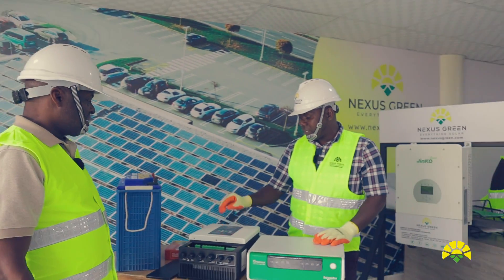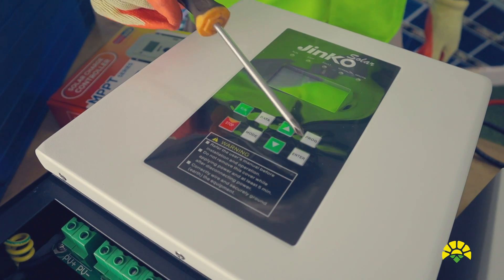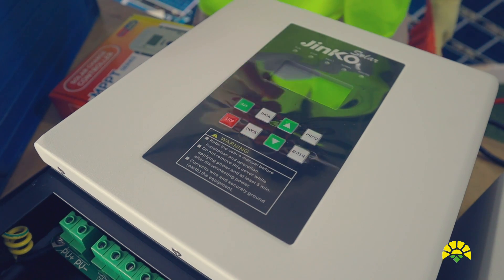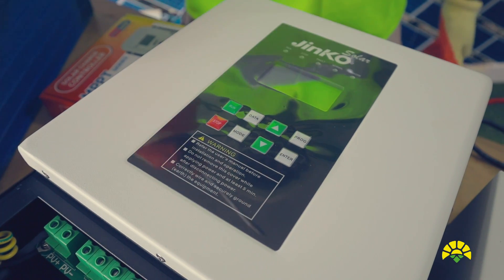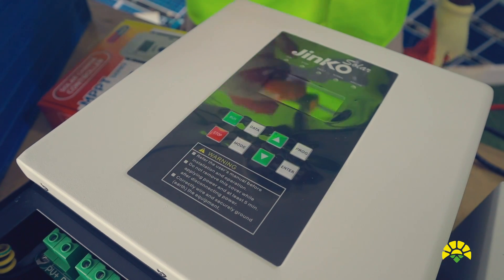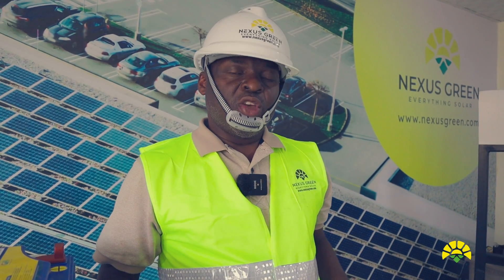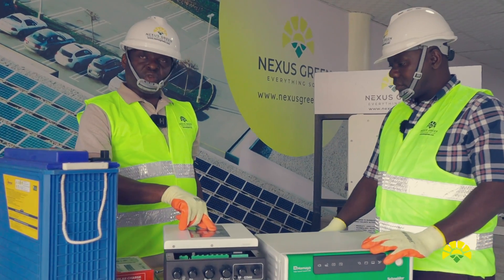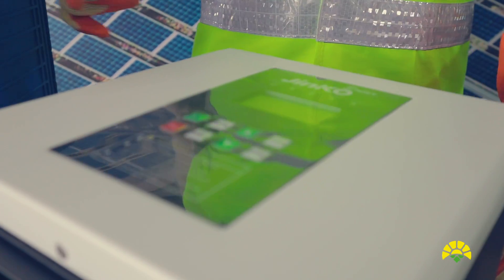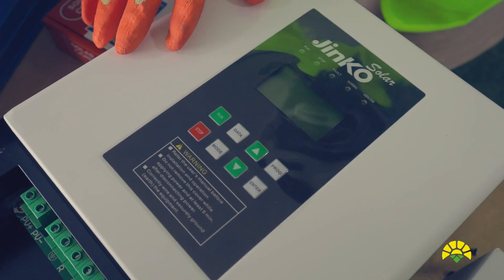Looking at the display panel, the parameters you're likely to see — this display module has run button, data, program, enter, mode, and stop. For operation purposes, the operator only needs to press run to start the pump or stop to halt the pumping. For installers, the other buttons are used to configure the inverter to adapt it to the solar panels installed, the pump connected, and all the sensors. You press the program button and use the manual provided to program the inverter.